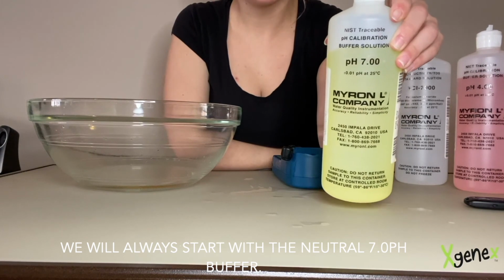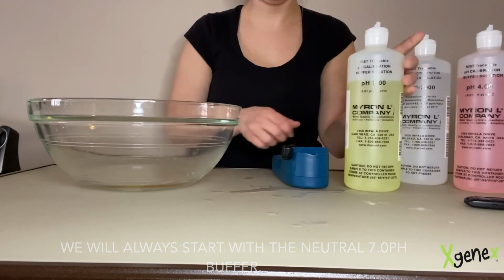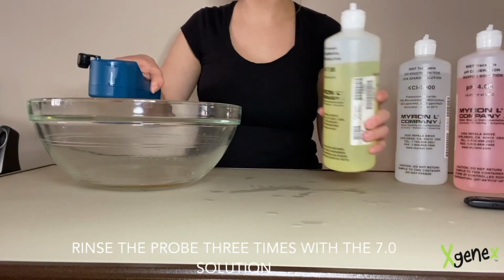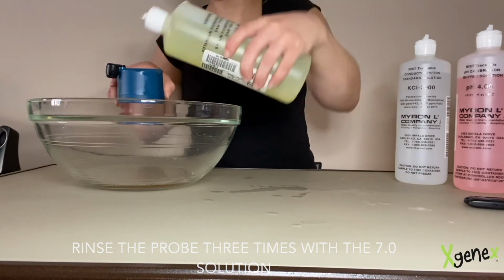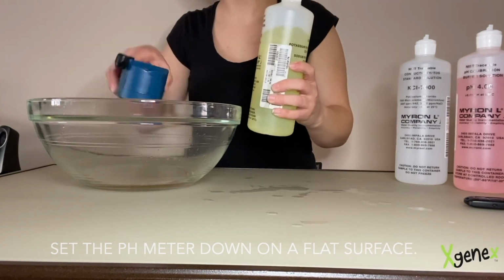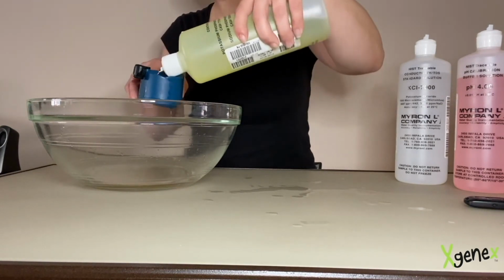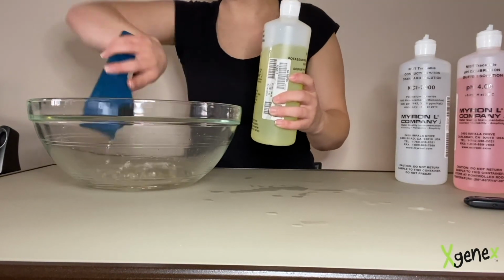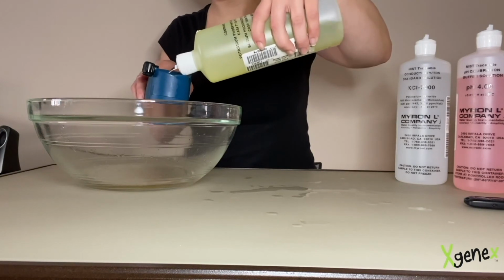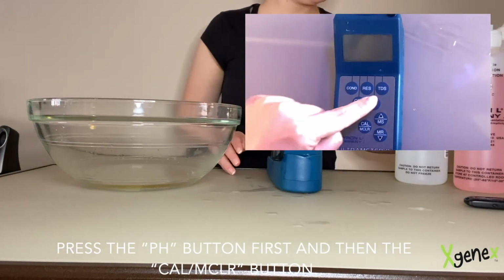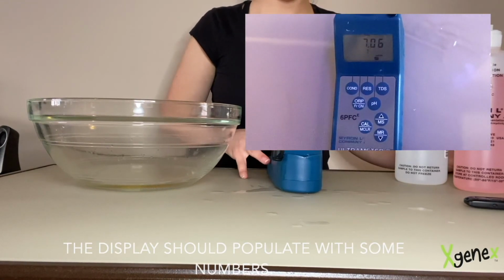We will always start with the neutral 7.0 pH buffer. To begin the calibration, rinse the probe 3 times with the 7.0 solution and then fill the sample well. Set the pH meter down on a flat surface. To calibrate the meter, press the pH button first and then the Cal button. The display should populate with some numbers.